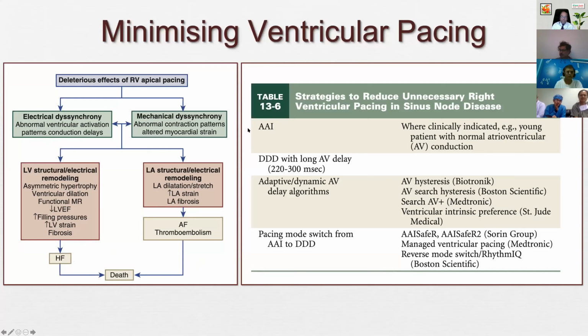That's why we like to do either an atrial pacemaker or a DDD with long AV delay. Or other strategies are to use algorithms which minimize the ventricular pacing, like AV hysteresis or AV search hysteresis, or sometimes we have very specialized algorithms within the pacemakers. Like all manufacturers have certain algorithms like AAISafeR from Sorin Group, managed ventricular pacing from Medtronic, reverse mode switching from Rhythm IQ, and of course we have ventricular intrinsic preference from St. Jude Medical. So every manufacturer has algorithms to minimize the RV pacing. So these things are very important to determine.